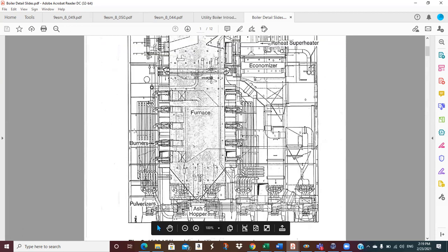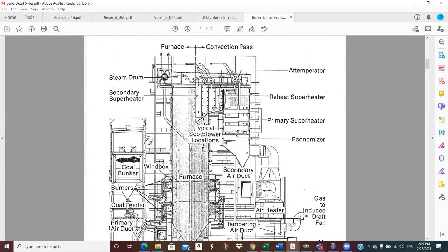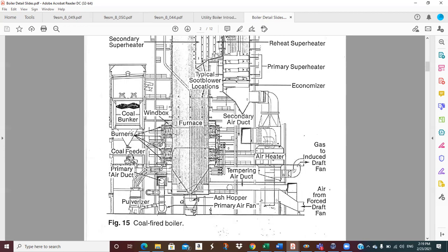So we've got some diagrams that show this a little bit better. But this is just another diagram. This maybe is a little bit better, a little clearer. These are conveyor belts that run up high. So after the coal crusher, the conveyors run up here to the top, and they can fill the individual coal bunkers. And so this will be a day or two supply of coal. And then as it's needed, it falls down to a feeder and then into the pulverizer and then gets blown into the furnace. Wind box is ducting that provides additional combustion air.